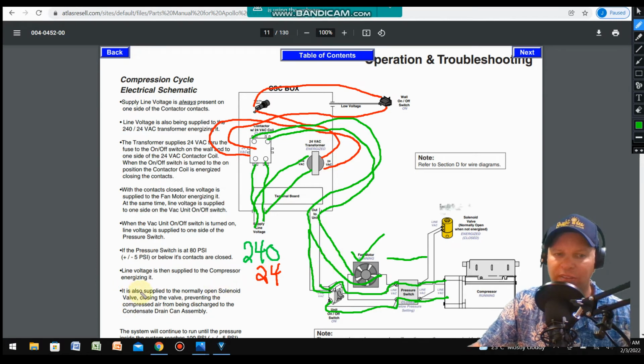part, or you could repair that part. So it's also supplied to the normally open solenoid valve, closing the valve, preventing the compressed air being discharged to the condensate drain assembly. So at the same time that everything is being supplied to the compressor, you have a parallel circuit that comes up here, and this is a normally open solenoid. And this is really important because when it's energized, it's not going to allow the air to escape from the piping on the compressor. Vice versa, when this pressure switch closes, the solenoid valve that's normally open returns back to an open state and allows air to bleed out of it and allows the purge cycle to happen.